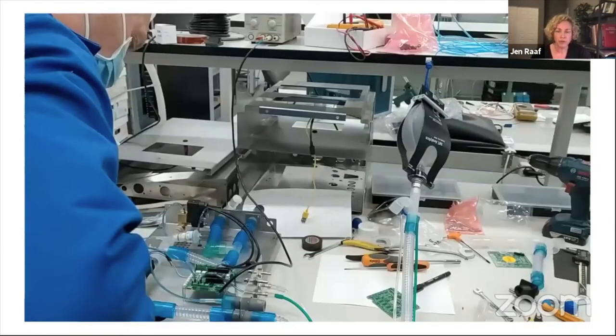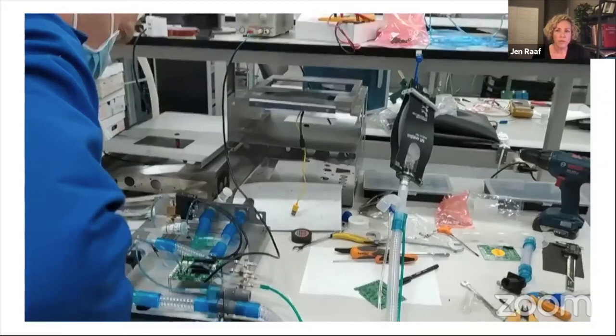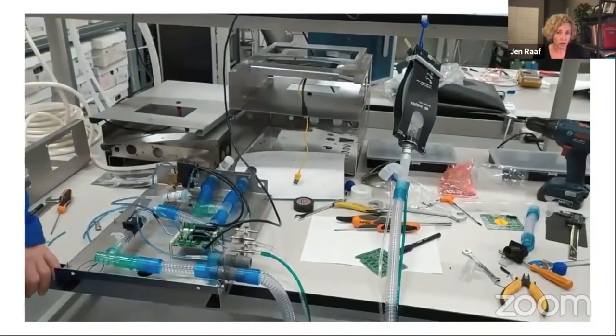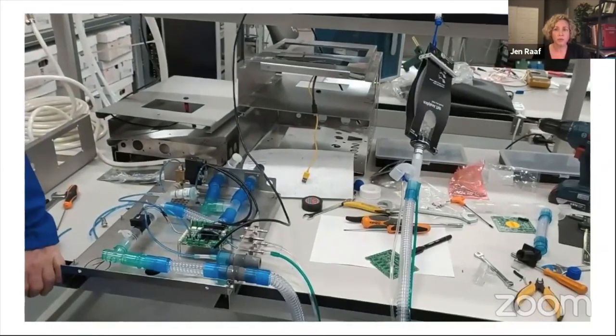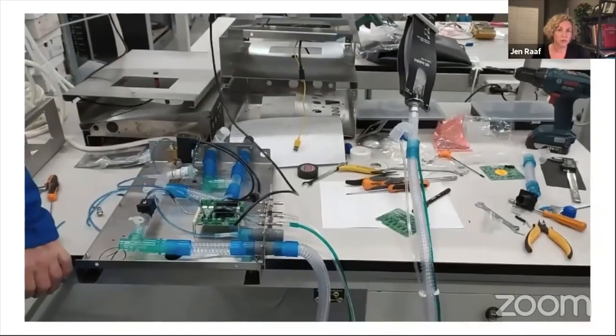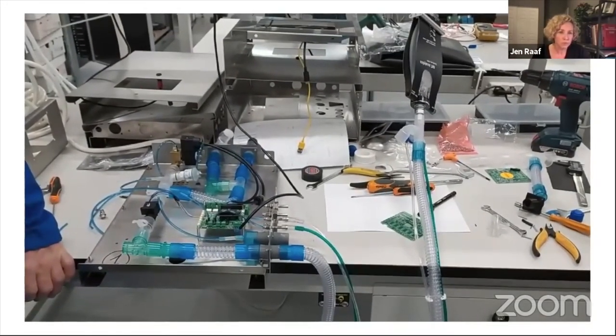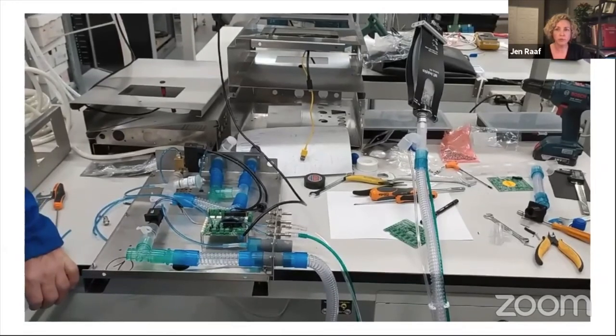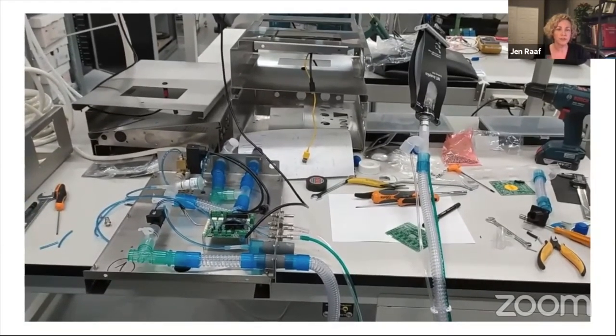In our second prototype, we eliminated the temporary water column method of setting pressures and moved to electromechanical regulation. The corrugated clear tubing and the blue and green parts you see are standard patient breathing circuit tubing used with ventilators and anesthesia machines, which hospitals have a large supply of. So our original idea was to use those types of parts to keep the cost low.